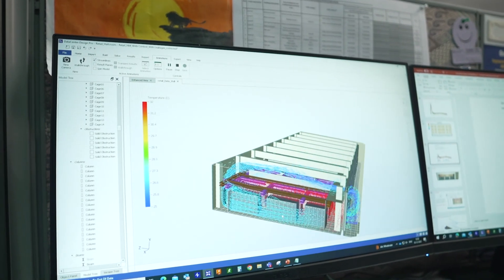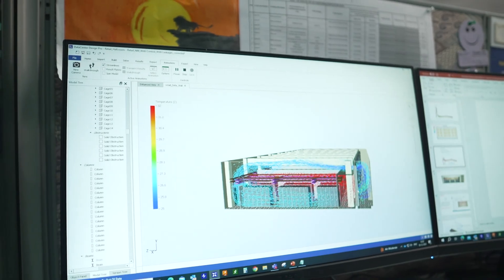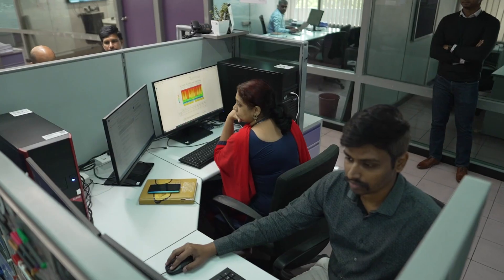We need a tool while designing to ensure that the cooling system designed would be very effective for different modes of operation of the data center. We needed to do a detailed 3D analysis of airflow and heat transfer in data center design, and conduct what-if scenarios to ascertain design effectiveness for data center server rack cooling.